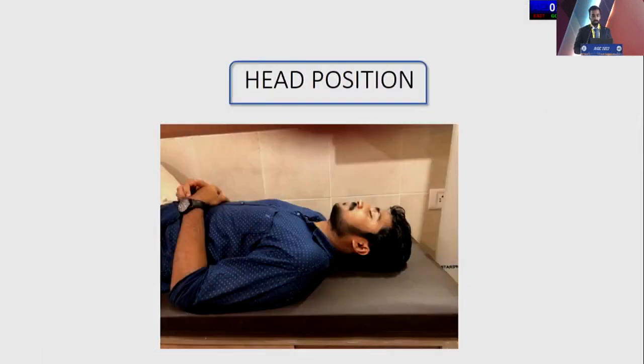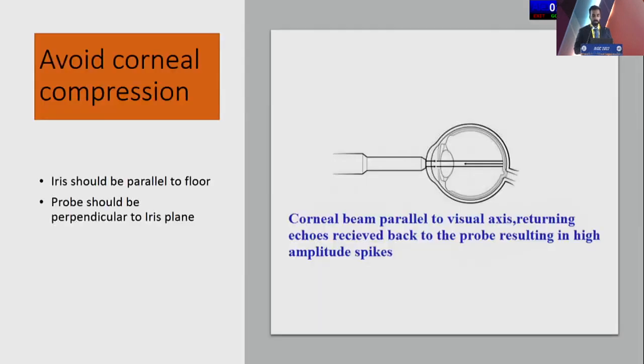So this is the example of a correct head positioning. As we see here, the head is absolutely flat. The iris will be parallel to the floor. And now when you go ahead and place your probe perpendicular to the iris, you will get a good axial length measurement. So as I said earlier, the idea is to avoid corneal compression. The iris has to be parallel to the floor with the probe perpendicular to the plane.